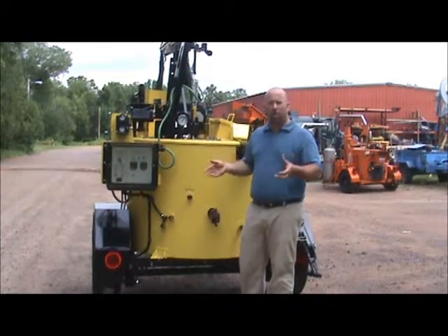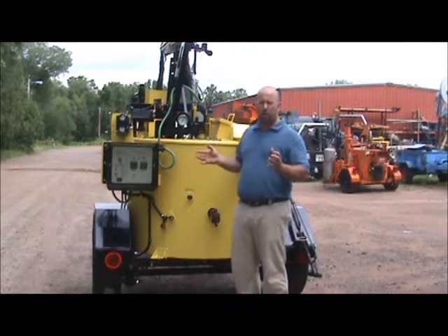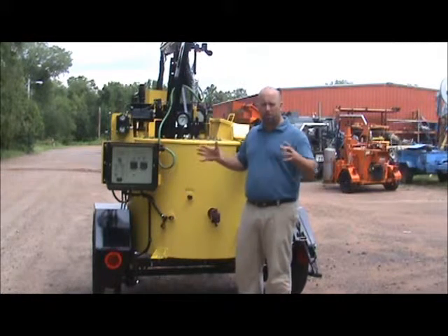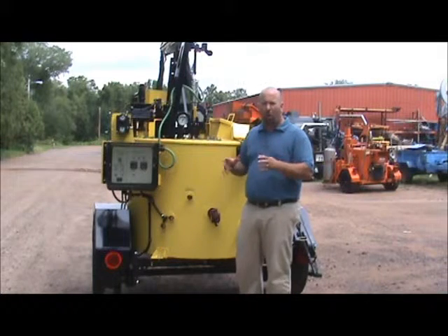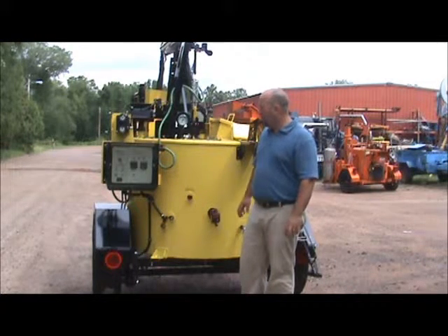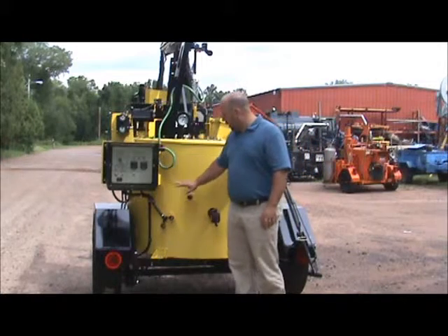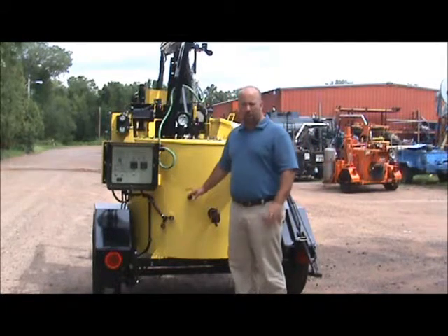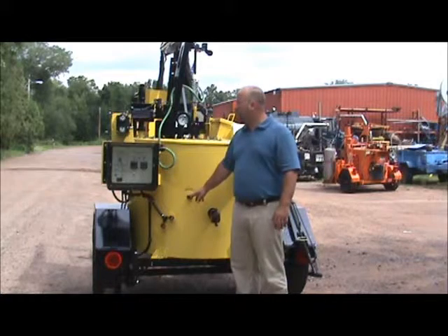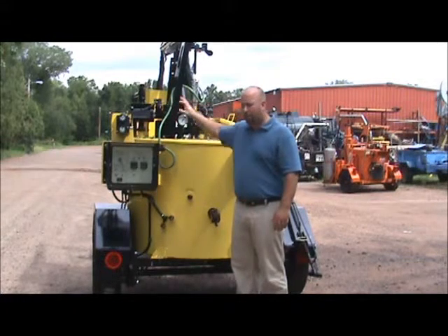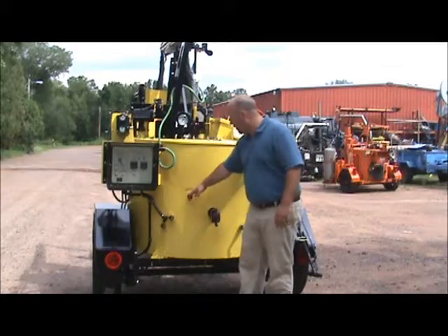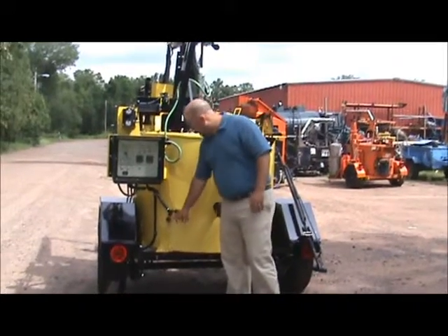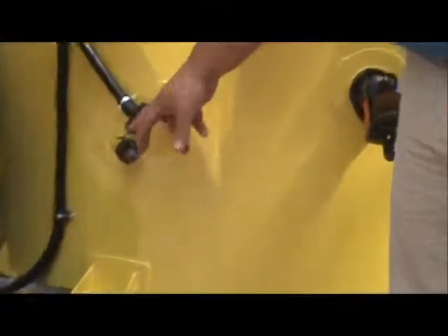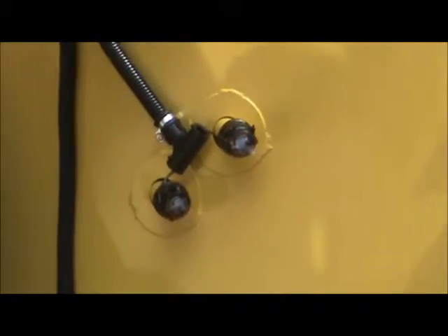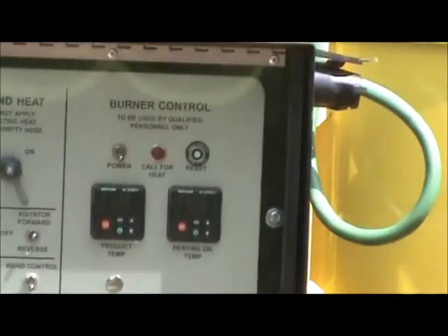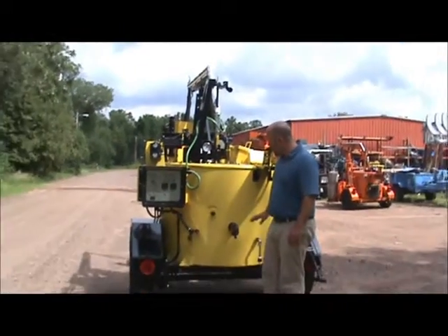Once the oil's up to temperature, the burner is going to shut off. Once the burner shuts off, even though our product's not up to temperature, we're still heating it because we're heating that up with our oil. It's kind of built like a boiler. Our cold fill level, if you change the oil, if you're adding oil to it, there is a dipstick also located up on the top here, but your cold fill level is here. We've got 2 temperature probes here. The bottom temperature probe is your oil, the top one is your product. That's what gives us our temperatures on the thermostats themselves. So that reads the temperature inside the tank.